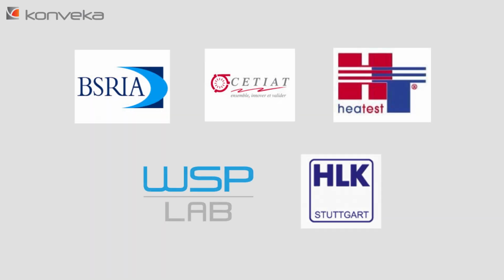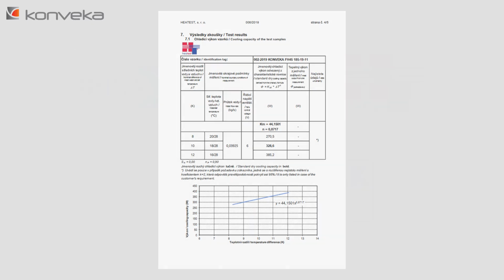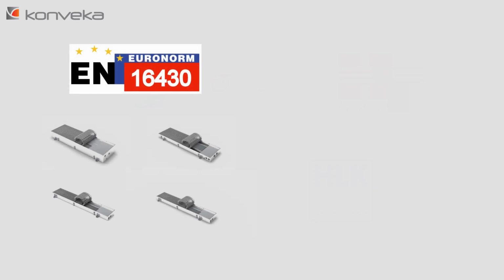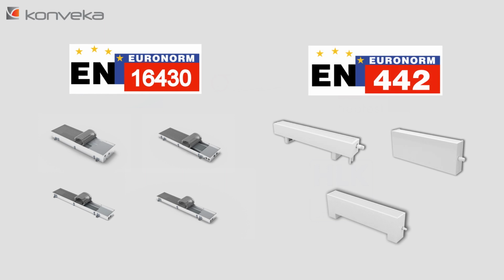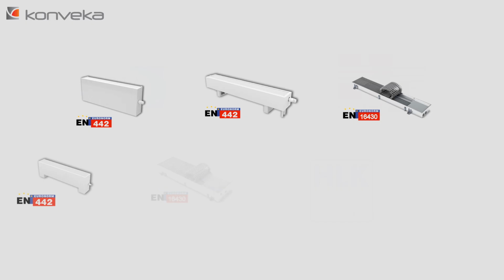We can trust the data only if the manufacturer has verified the output of its products in an independent, accredited laboratory and has test reports that conform to the effective standards, such as International Standard EN 16430 for heating and cooling trench heaters and EN 442 for freestanding and wall-mounted convectors. All Konveka products are tested by independent accredited laboratories and have output measurement reports that are compliant with the applicable standards, so the outputs indicated are completely reliable.